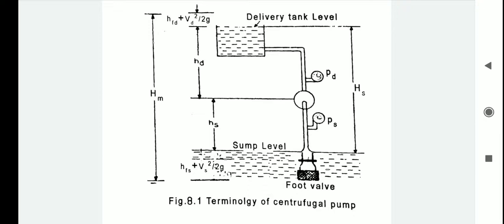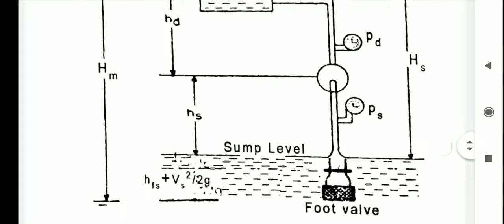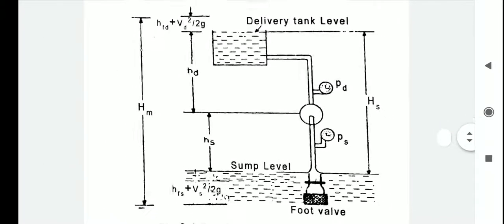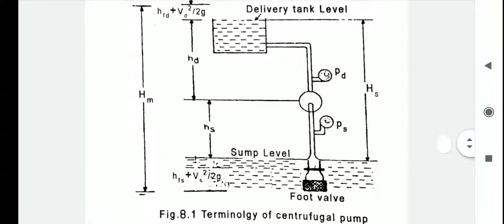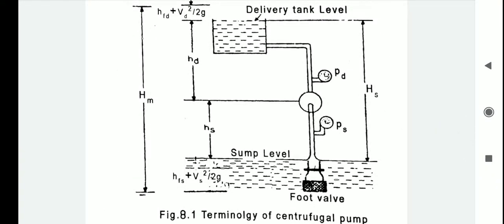The first one is suction head, that is hs. As you can see from this figure, it is the vertical height of the center line of the pump above the water surface in the sump. This height is called the suction lift and it is denoted by hs.